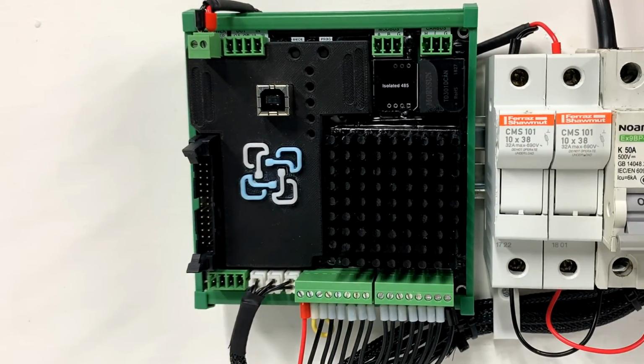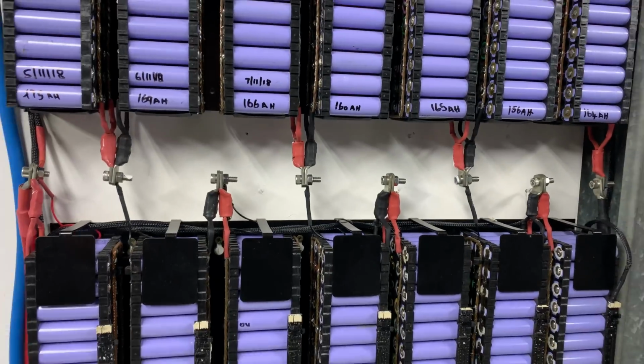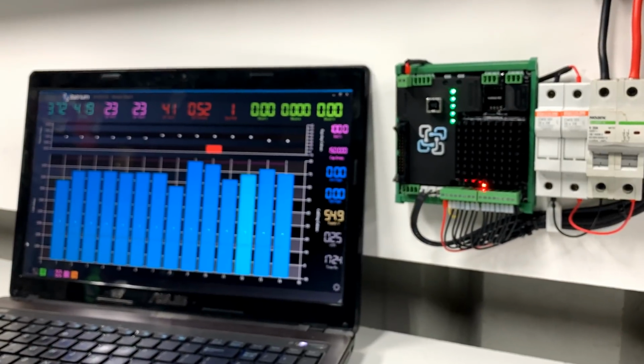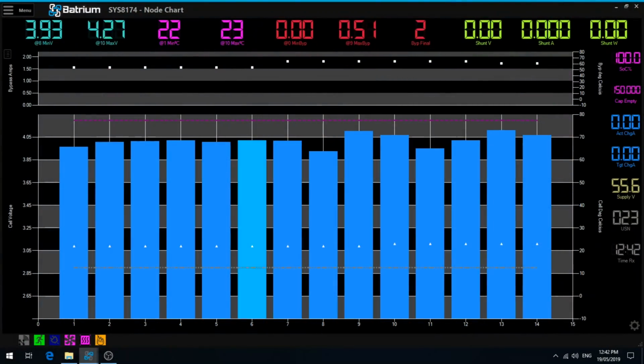Install the 3 temp sensors and run them to the top, middle and bottom of the battery to finish up the wiring for now. With the install complete, as you can see, the battery is very out of balance due to replacing some cells recently. I'll be boost charging the lower cells with an additional charger to speed up the process for this video.